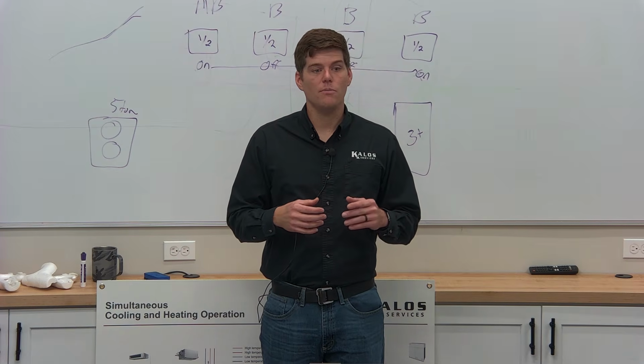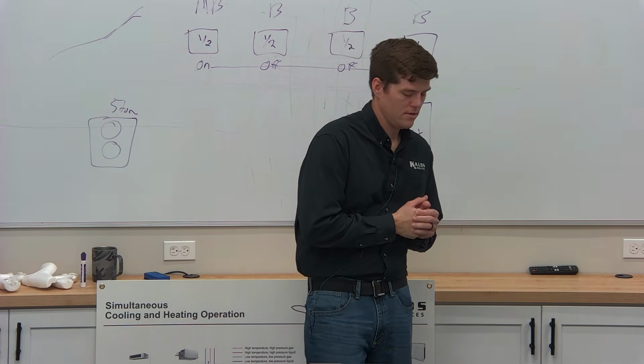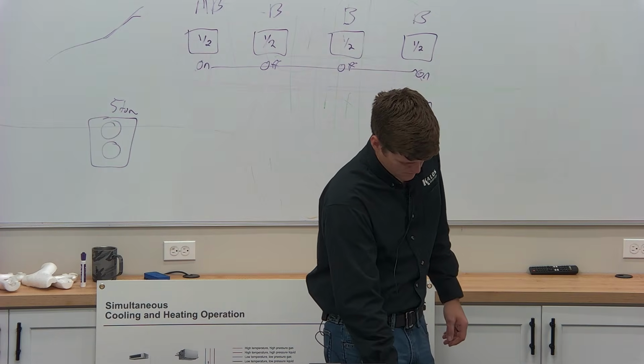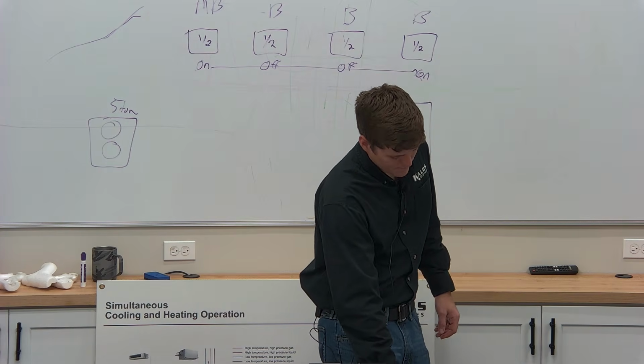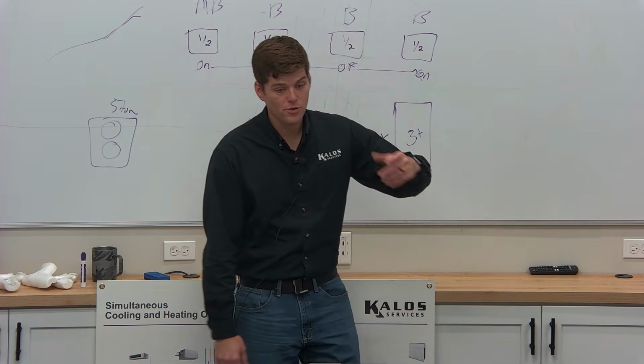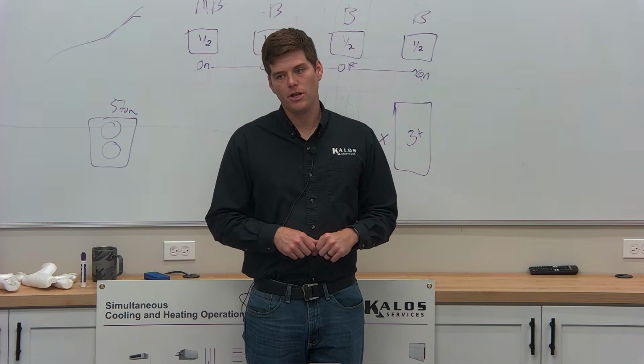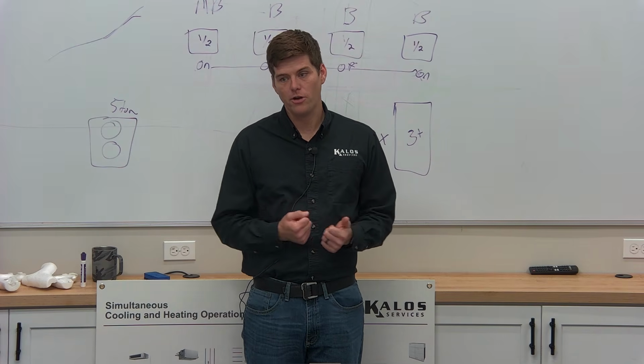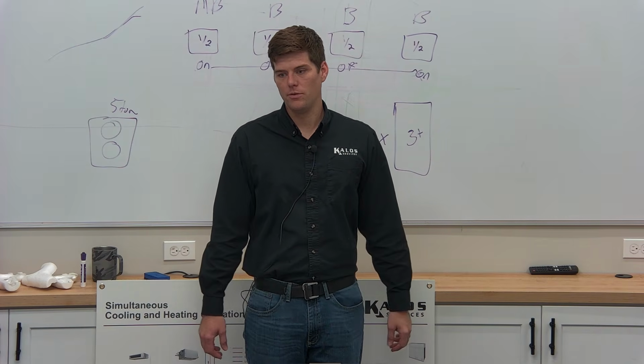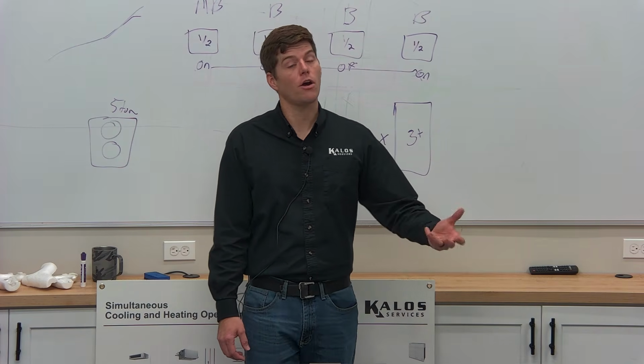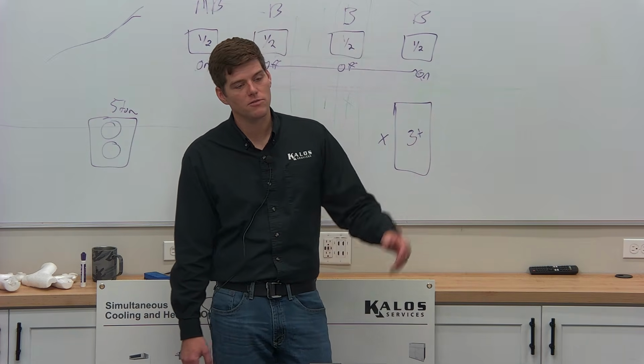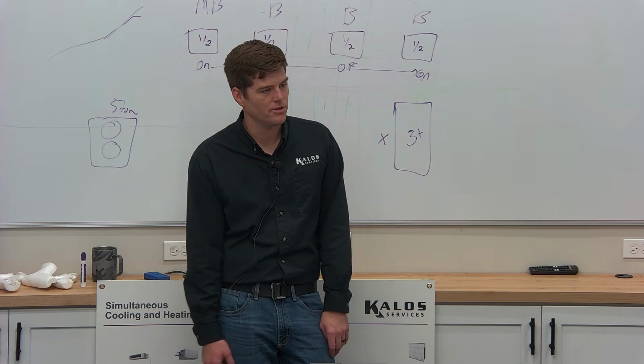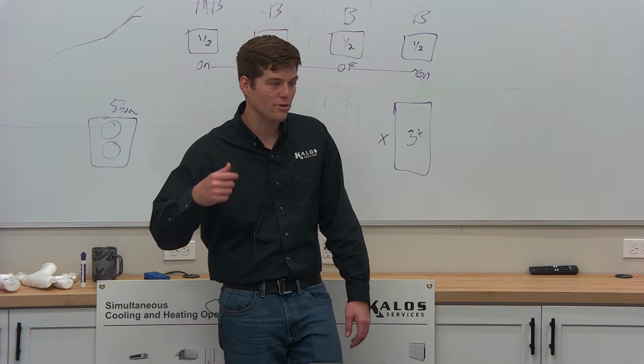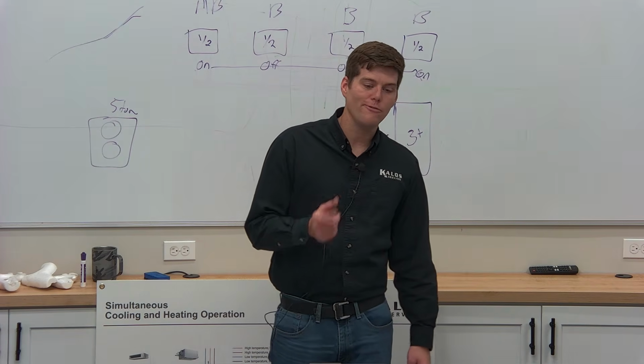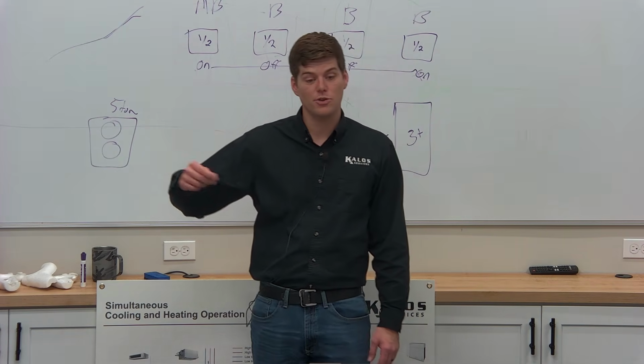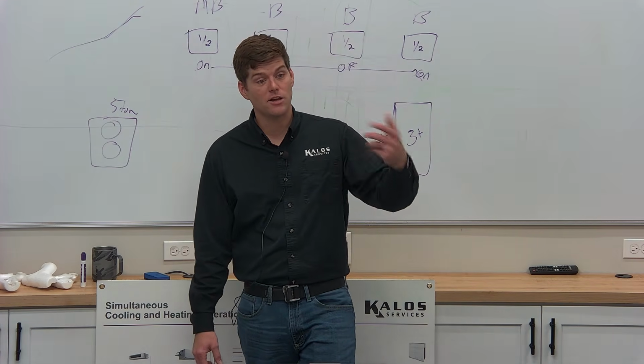They're pretty easy as long as you pay attention and follow through with what you're doing. So if you put Nylog on it, you put a lubricant on it, then sure, you could actually slip it farther than it's supposed to go with a torque wrench. Maybe not that much farther, but a proper flare doesn't require any kind of other sealing material. It doesn't require thread lock or thread sealant. And you'll find the bad mechanical contractors when you go to the inside unit and find that it's covered in pipe dope.